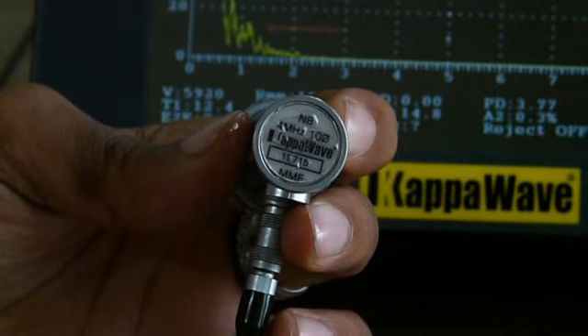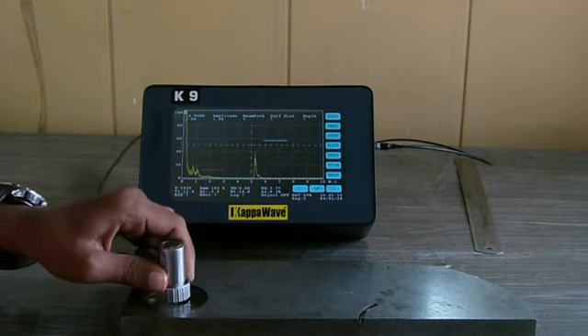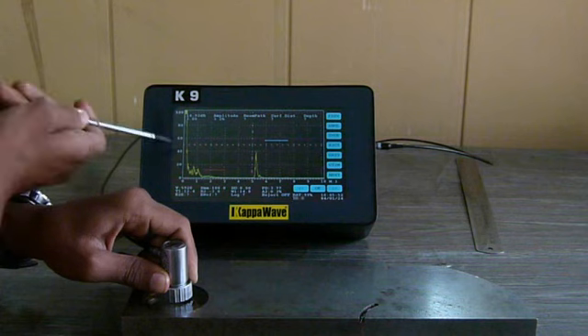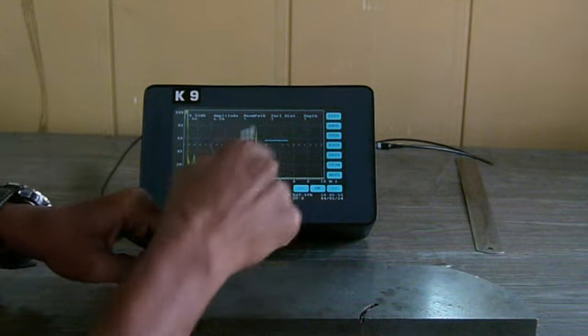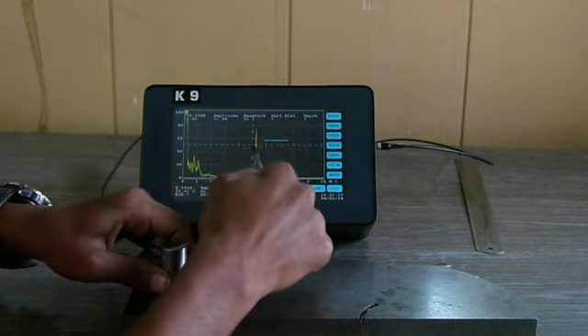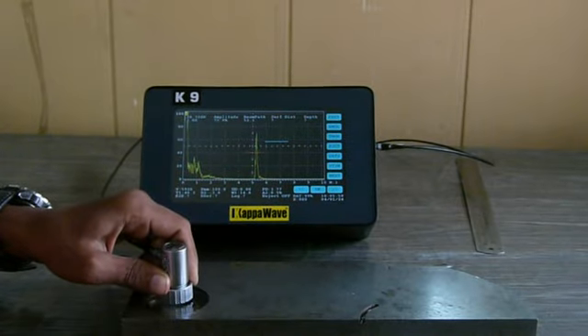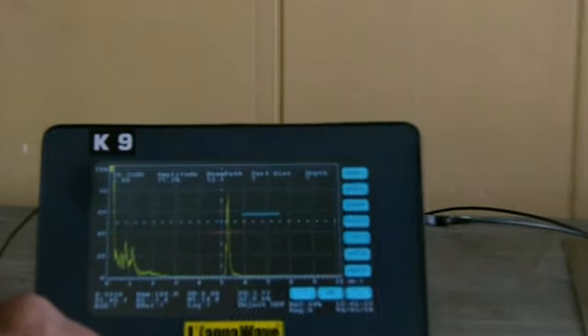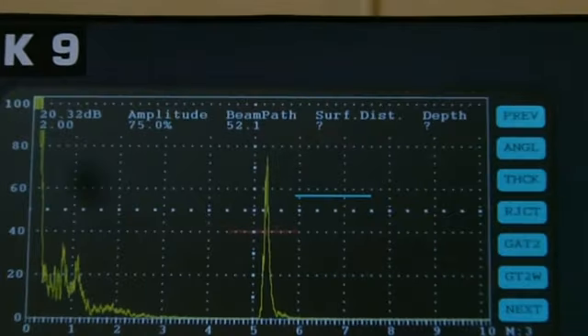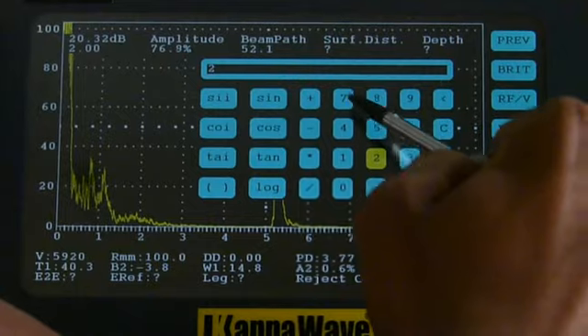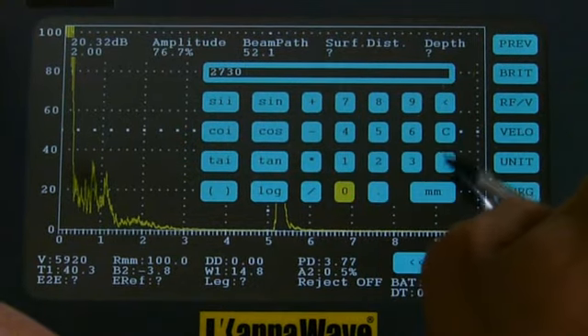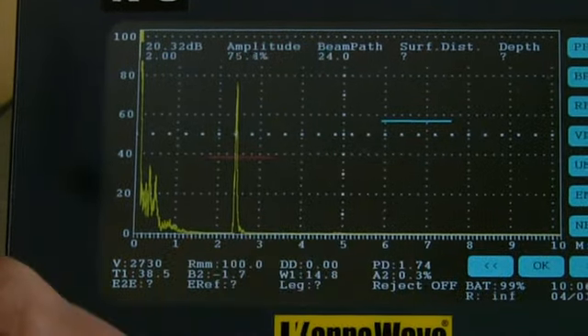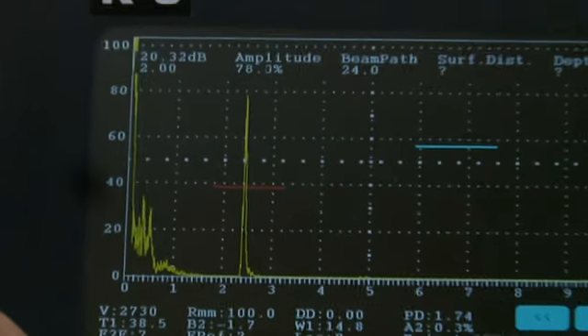Using the same range calibration, we will use this probe to measure the thickness of the perspex insert on the V1 block. It is read as 52 millimeter. Now we will change the velocity on the instrument and see what the actual thickness of this is. We will change it to 2730, and now the thickness is read as 24 millimeter.